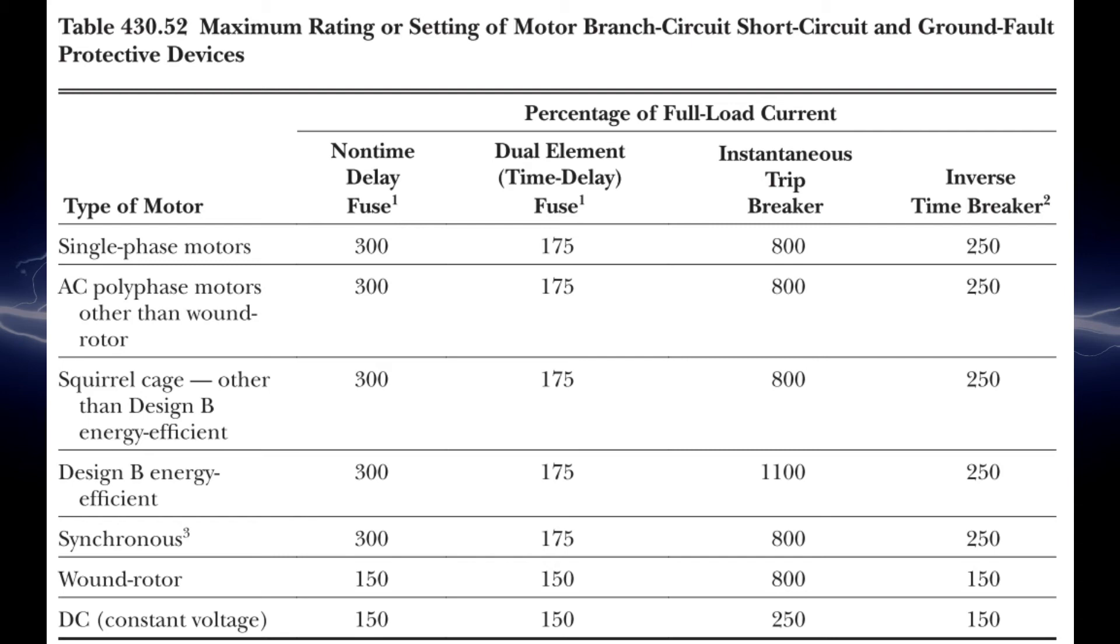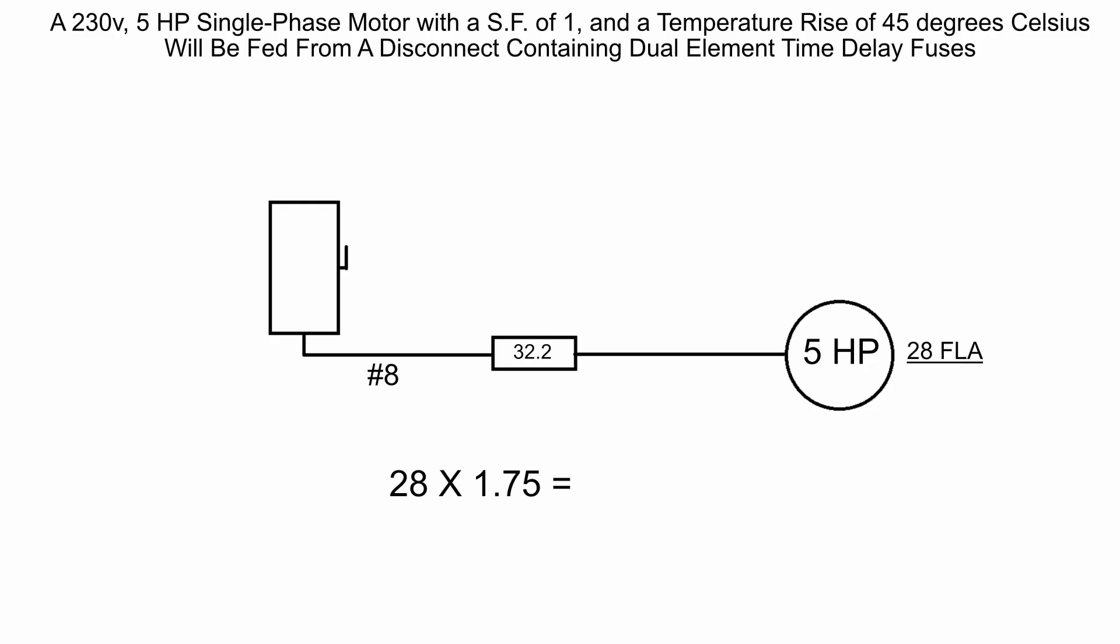In the first line we'll see single phase motors. We're using a single phase motor so that's the line we're going to use. We'll see under dual element time delay fuses 175 percent factor that we're going to use to determine that. We'll say 28, the full load amps, times 1.75 is going to give us 49 amps, which is what we're going to use to size the overcurrent device.